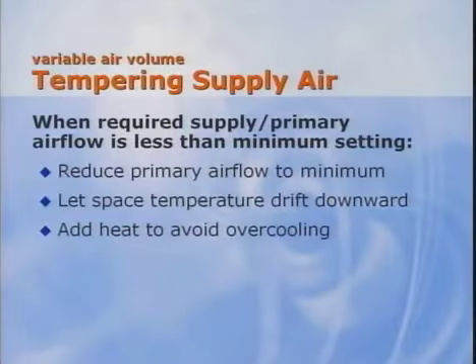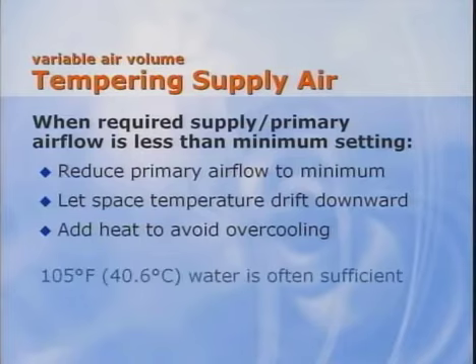Finally, let's look at a variable air volume system. The coil supply air temperature is constant, and variable air volume is used to control the space temperature. In most applications, each VAV terminal has a minimum airflow setting. For example, it may be set to maintain the zone's ventilation requirement. If the space load drops far enough, this minimum position may cause the room to overcool. Heat recovery can be used to maintain proper space conditions. Many times these heating loads can be met with water temperatures of 105 degrees Fahrenheit, as supported by ASHRAE. Again, an ideal application for heat recovery from any chiller.